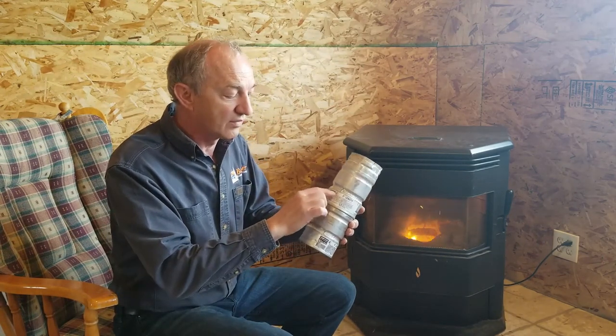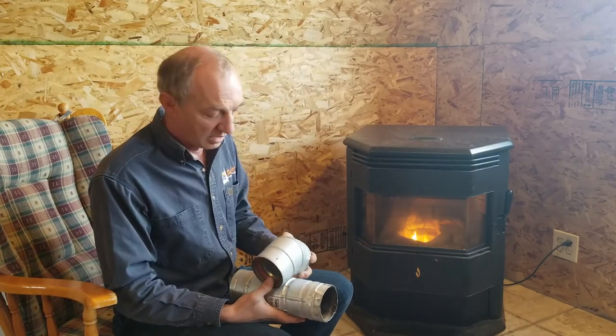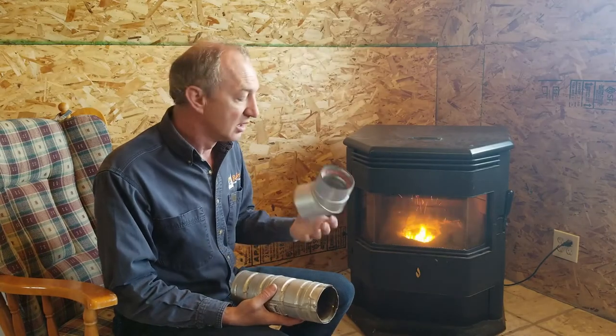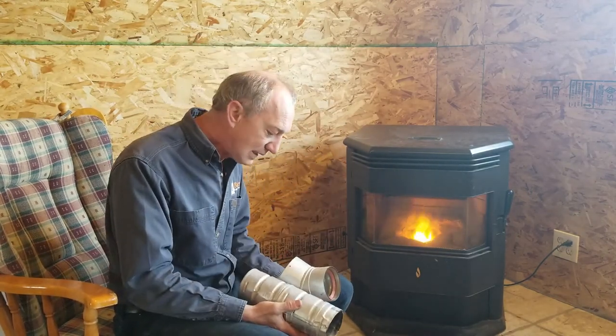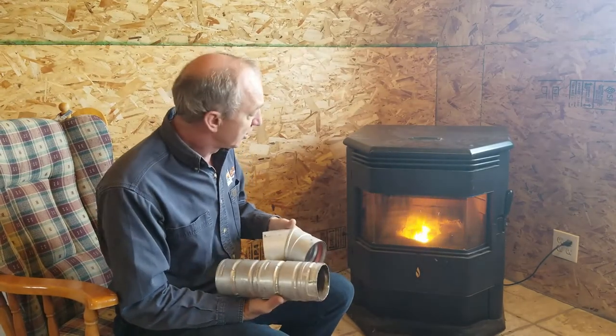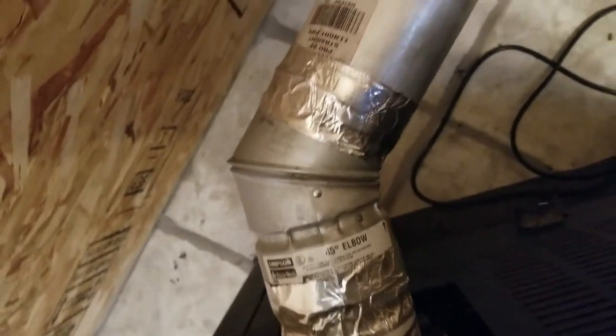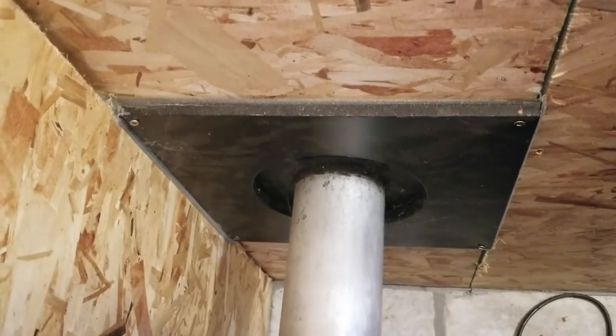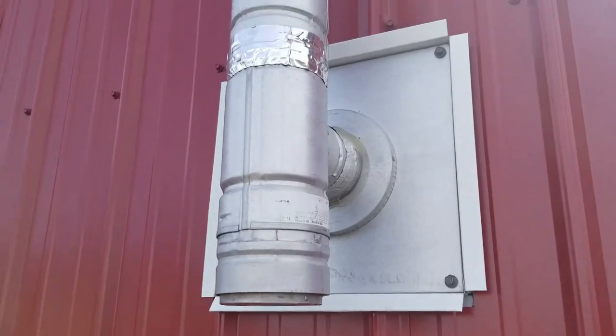The important thing is that the venting is certified — in this case ULC and Warnock Hersey — for use with a pellet stove. You must also ensure the manufacturer approves the chimney for use with your specific appliance. In my installation, the chimney exits the back of the stove, uses a 45-degree connector, passes through a certified wall thimble, then goes up and through the roof — with a clean-out at the base.